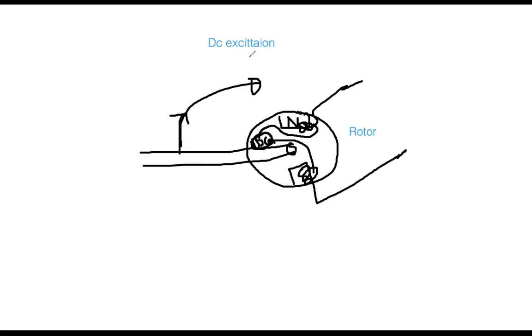AC excitation means, instead of that DC generator, the system has AC. On the shaft there is a small size AC generator. And of course here there is the requirement of DC. Always keep in mind, for any magnetic field, you must provide DC to get a steady flux, to produce a steady flux. That is the DC.